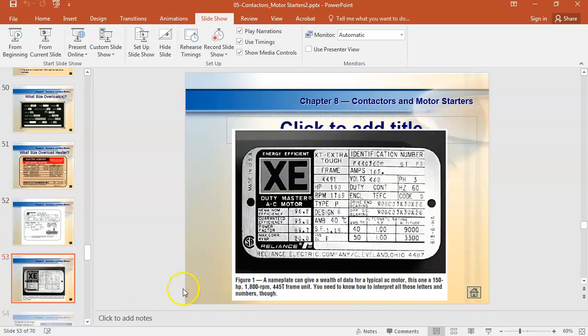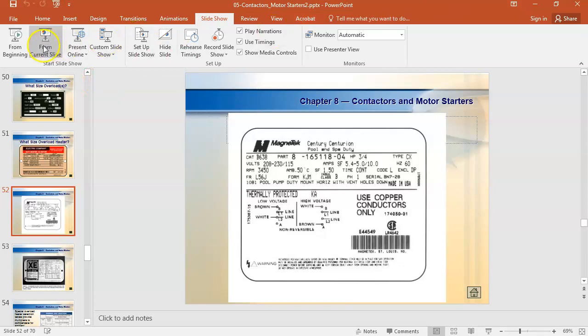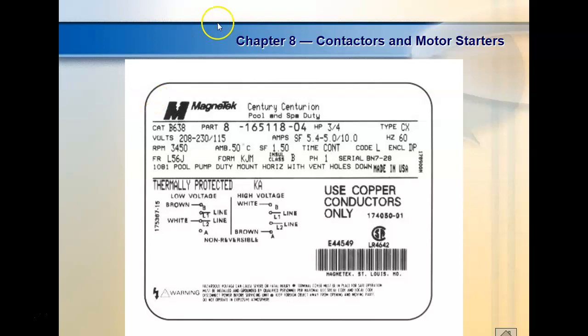Okay, guys. What about this guy? So it's got a service factor of, yeah. So we've got no problem with that. And it's half an amp, right? 500 milliamps. Can you see the period? No, that's ambient temperature. Here we go. Yeah, 5.4. I don't even see the service factor is 1.5, so I don't know what that is. 208, that's what we have. So yeah, 5.4, 208.